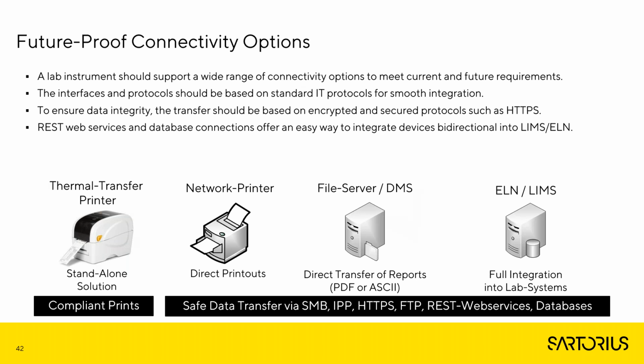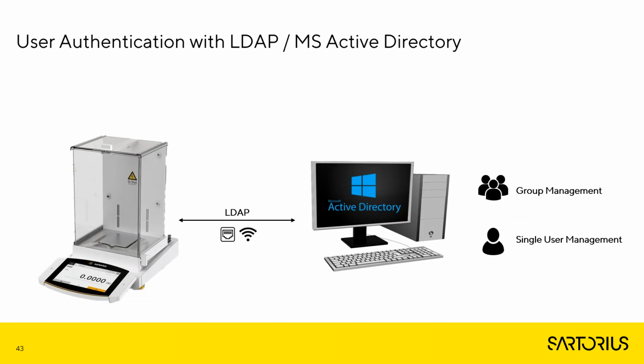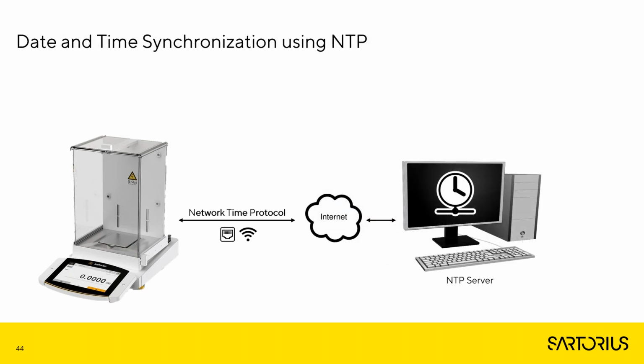Please, next slide. Okay, so in this slide, you see the communication between the Cubis II balance and the Active Directory server, where the user accounts are stored. For that, you basically need the Ethernet or wireless connection. Next slide. This is a time synchronization protocol. So the only thing you need is the connection. The balance has to be in the network, on the wireless network or with the Ethernet cable, and you then configure the NTP server, and your date and time are synchronized automatically. Next slide.